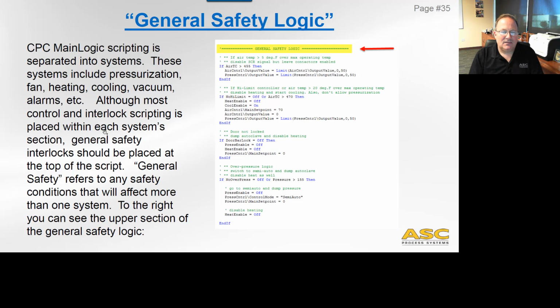the general safety interlocks should be placed at the top of the script in their own section. And so we're going to call that general safety logic, and you should put a big header like this, general safety logic. And general safety logic refers to any safety condition that will affect more than one system. So what you'll see here is most of these conditions will not only affect the temperature but also pressure conditions of the autoclave. And so we're going to call those general because they're going to be one safety condition which is affecting a lot of things, okay? And we're going to put that at the very top of the script.